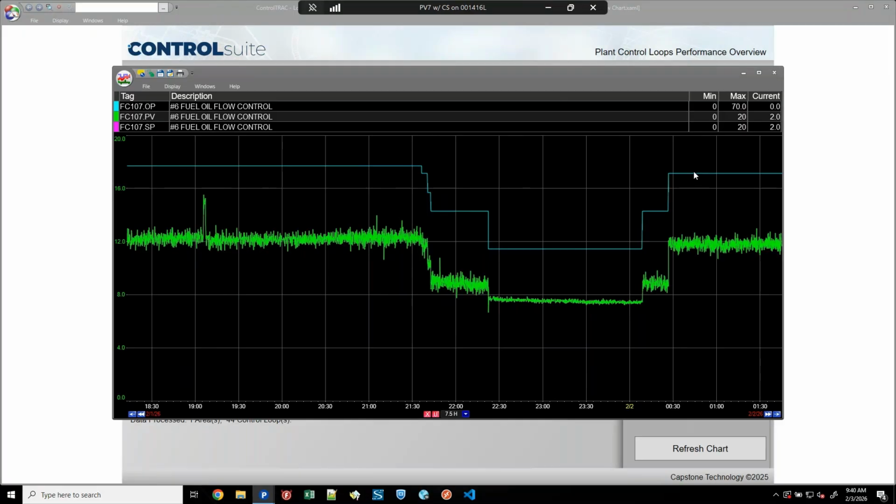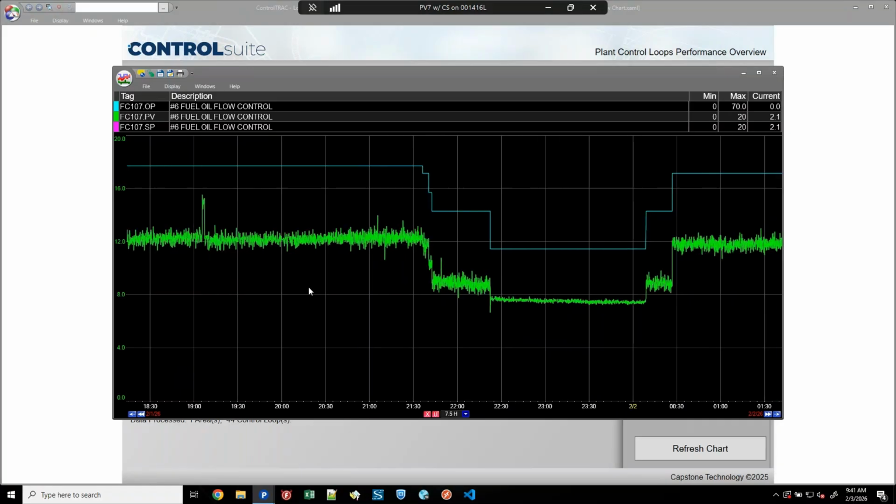It's important to ensure there are no upstream disturbances. So while you're doing this bump test or step test, you want to make sure you're not increasing your production. You want to make sure there are no additional flows that could cause disturbances, nothing that's oscillating. Try to hold everything as steady as possible, because the goal is we're going to build a step response between our output and our PV. So if you have disturbances that cause your PV to move around, that would interfere with your step response. And whatever data we have in our trend is going to be used for tuning.